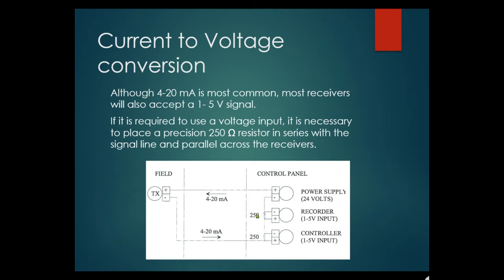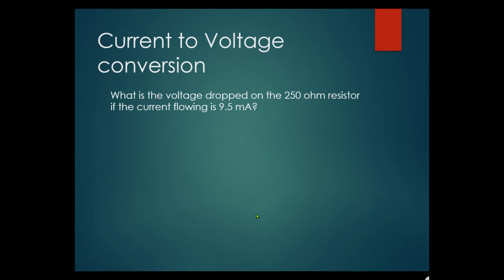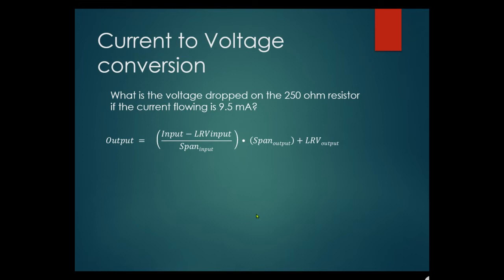If you have other than 250 ohms it won't work correctly. Also, if you're going to put on a communicator, you need a minimum 250 ohm resistance on a loop so that communicator can actually function. Current-to-voltage conversion: what is the voltage dropped on the 250 ohm resistor if the current flowing is 9.5 milliamps? You can use the input-output formula or simply Ohm's law — if you know the milliamps and the ohmic value, you can calculate the voltage.